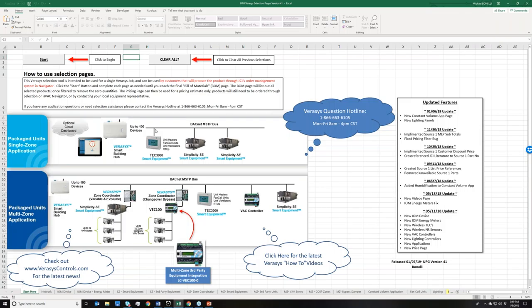We give you the opportunity to land that shield, so if you have it, I would definitely use it. If you run into a situation where there is no shielded wire, you can test the communication to see if it'll work, but there is no guarantee, and we do not guarantee that Verasys will not have communication problems. So long story short, if you have a shield, use it on not just the system bus, but also the zone bus and the sensor bus as well.